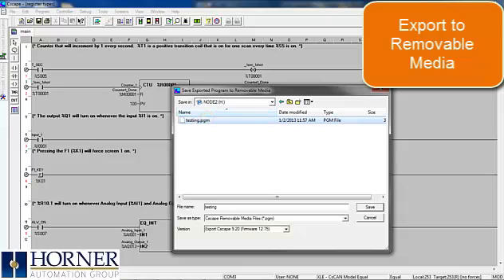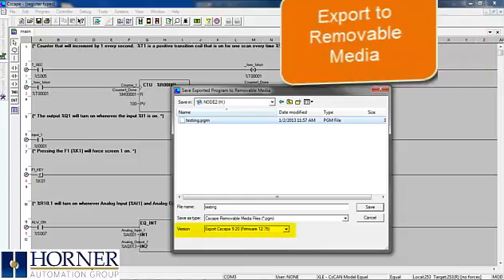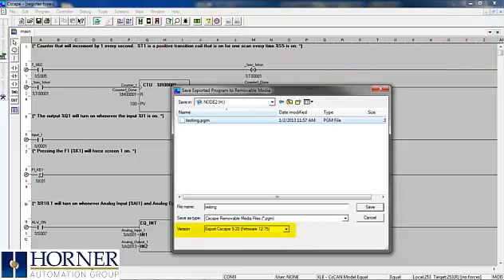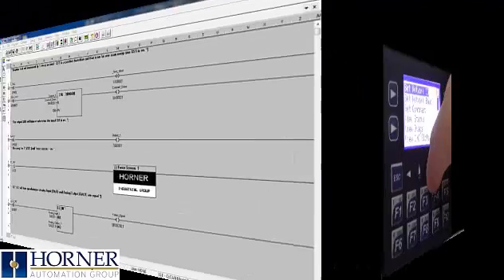As for selecting the version, verify the firmware version in the controller and select a version just below what is loaded into the actual controller. My controller has version 12.86, so I'll use version 12.75. Now you can save the file to the microSD card.